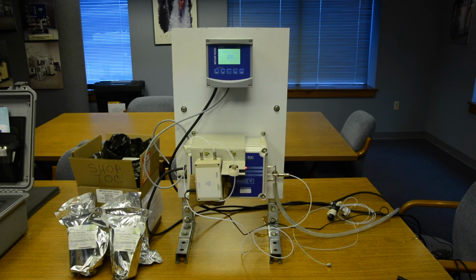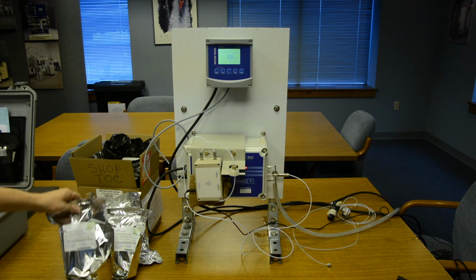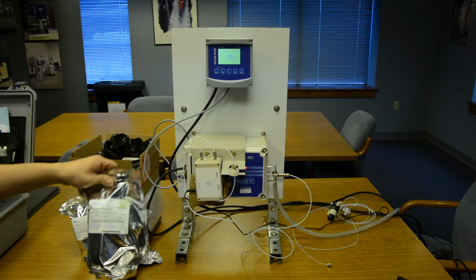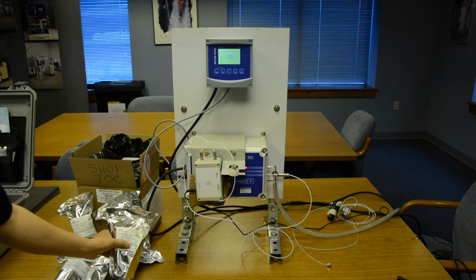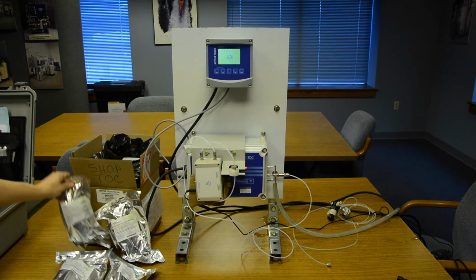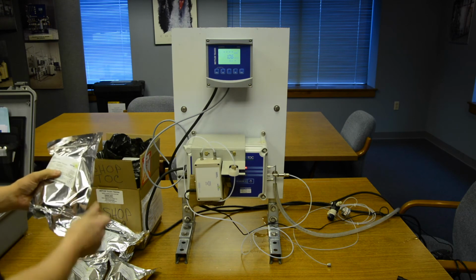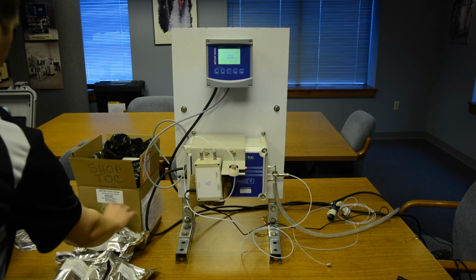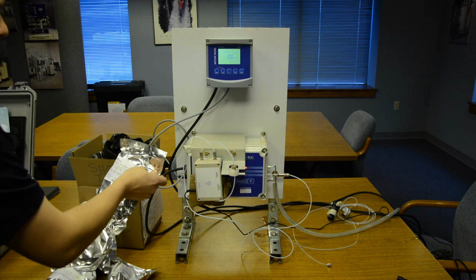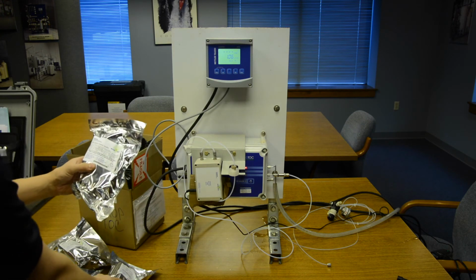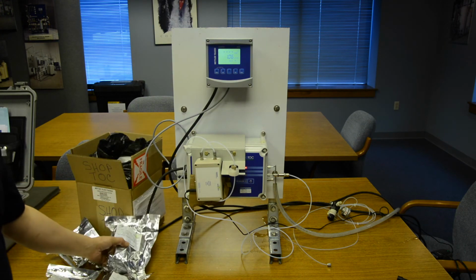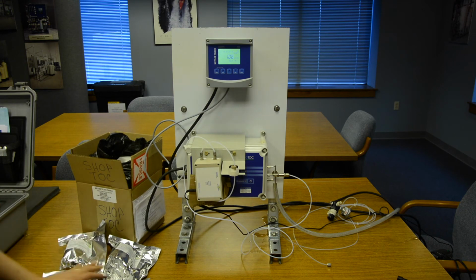The next set of solutions are for your suitability test. They include 4 solutions. You have 2 that are reagent water. They are less than 100 parts per billion. And then you have a 500 part per billion solution that's made from sucrose. And then another 500 part per billion solution that's made from benzoquinone. Those are the solutions that are needed for this calibration.